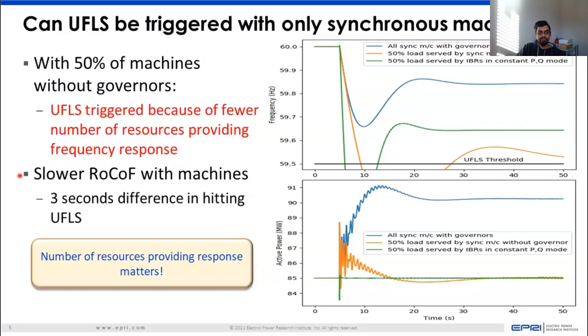A recap with respect to rate of change of frequency: the primary concern is hitting UFLS, or even a UFLS relay failing to operate or misoperating. If we look at synchronous machines, the rotating machine itself is designed to tolerate very fast rate of change of frequency, especially since they're also designed to tolerate voltage faults on their terminals.